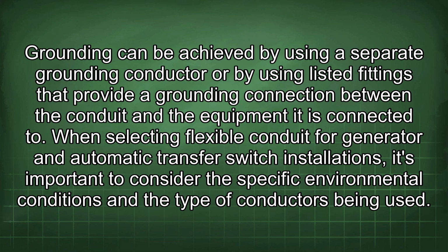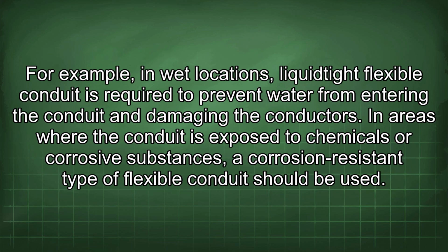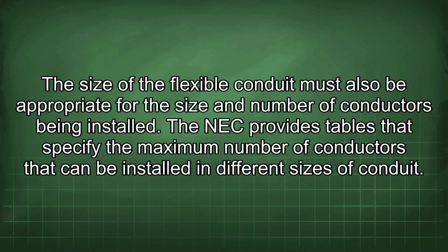When selecting flexible conduit for generator and automatic transfer switch installations, it's important to consider the specific environmental conditions and the type of conductors being used. For example, in wet locations, liquid-tight flexible conduit is required to prevent water from entering the conduit and damaging the conductors. In areas where the conduit is exposed to chemicals or corrosive substances, a corrosion-resistant type of flexible conduit should be used.